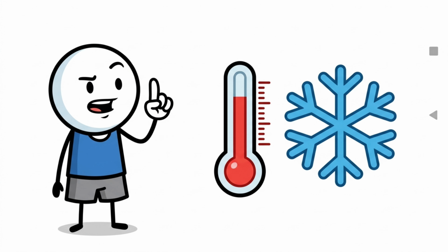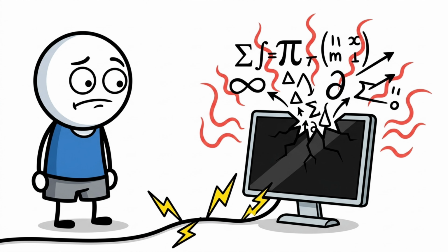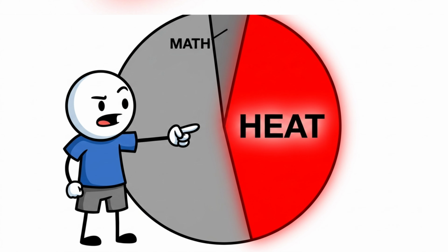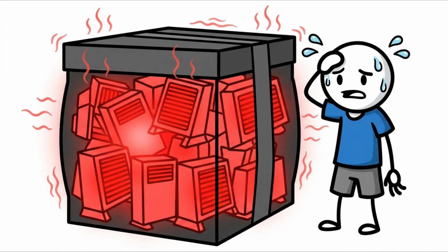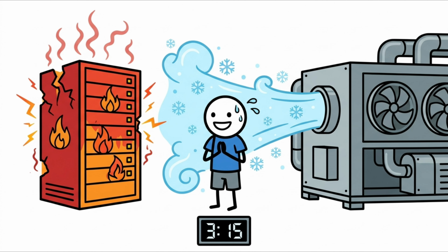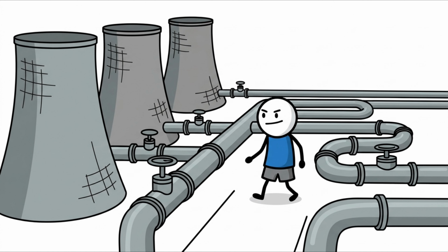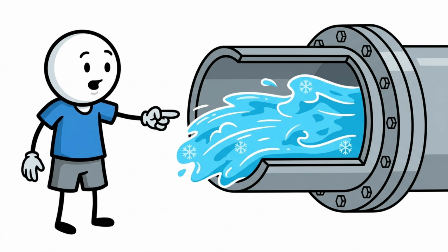Then you need cooling. Computers turn electricity into math and heat, mostly heat. A 50 megawatt data center generates the same amount of heat as tens of thousands of space heaters running at full blast inside a closed box. To stop the servers from catching fire, you need industrial chillers, massive cooling towers, and miles of reinforced piping pushing chilled water through the facility.